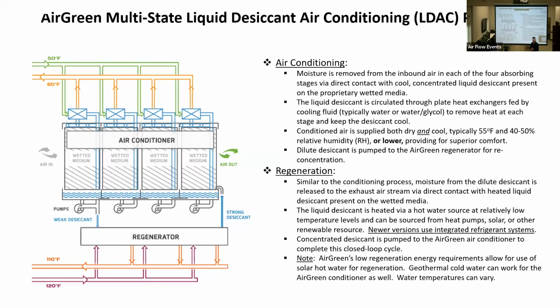You start to get into the refrigeration systems, and we've gone as low as conditioned air temperatures at 15 degrees and 2 grains of moisture. One pass directly from outside air. So that's very interesting to our refrigeration partner, as it reduces the number of steps required for makeup air systems and cold storage applications where you have to have outside air because humans work there.